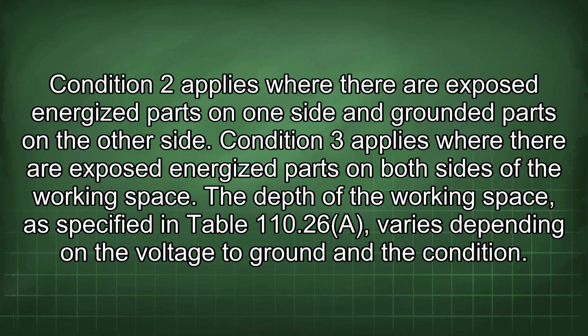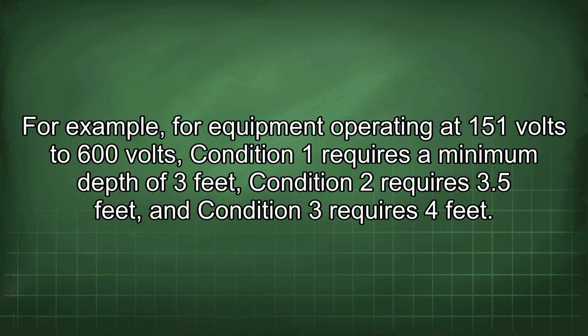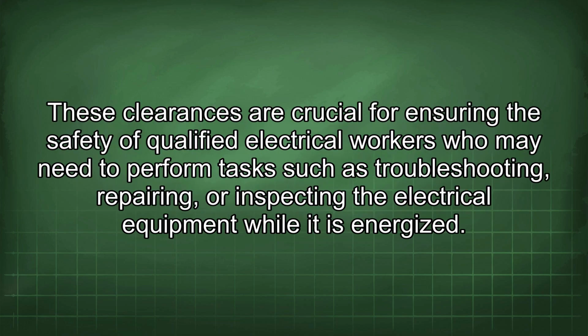The depth of the working space, as specified in Table 110.26(A), varies depending on the voltage to ground and the condition. For example, for equipment operating at 151 volts to 600 volts, Condition 1 requires a minimum depth of 3 feet, Condition 2 requires 3.5 feet, and Condition 3 requires 4 feet. These clearances are crucial for ensuring the safety of qualified electrical workers who may need to perform tasks such as troubleshooting, repairing, or inspecting the electrical equipment while it is energized.